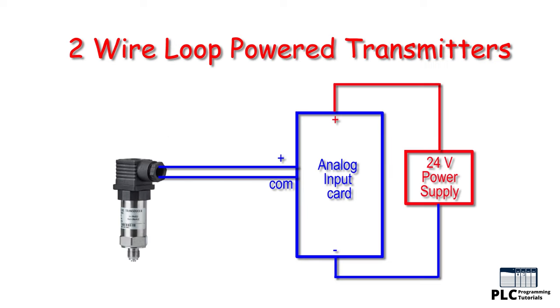2-wire loop powered transmitters: this configuration supplies power and the 4 to 20 milliamp signal over a 2-wire loop connection. Not all transmitters can be wired in this format — they must be specifically designed to accommodate this configuration. The advantages are low power consumption and that only a 2-core cable is required from the control panel to the transmitter.